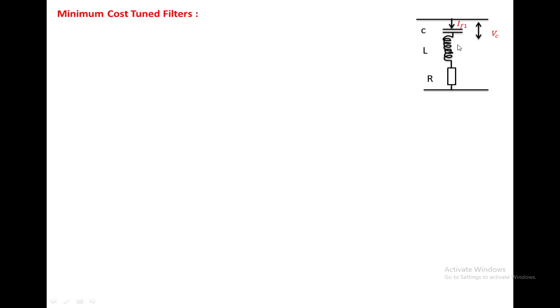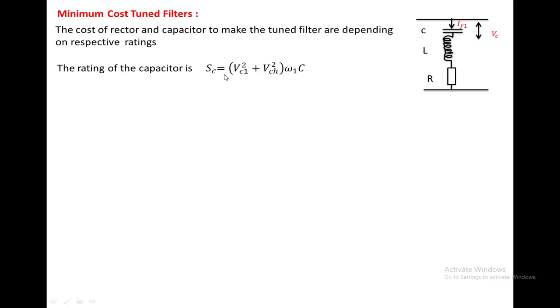Now we consider the minimum cost of the tuned filter. The tuned filter consists of a capacitor and a reactor, so its cost depends on the ratings of both. The rating of the capacitor SC equals the fundamental voltage across the capacitor plus the harmonic voltage across the capacitor, multiplied by omega1·C. The rating of the inductor SL equals (IF1² + IFH²)·omega1·L, where IF1 is the fundamental filter current and IFH is the harmonic filter current.